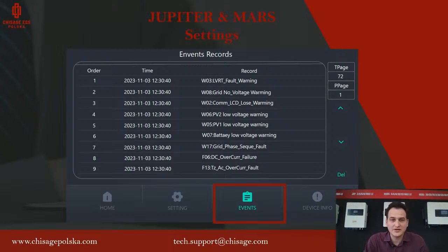So for example, if the inverter is working off grid, it will show a warning that there is a problem with synchronization with the grid. That's obvious, it will have a problem because there is no grid. So the warning will show, but the alarm will be turned off. That means the inverter knows that in off-grid mode, it doesn't care about synchronization.